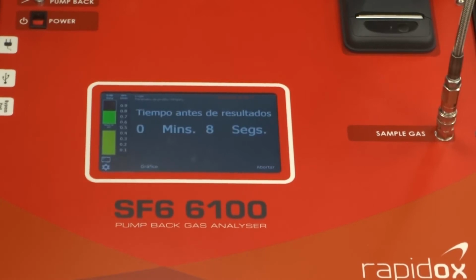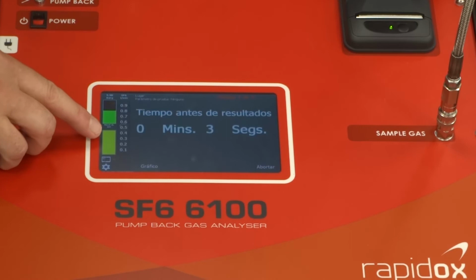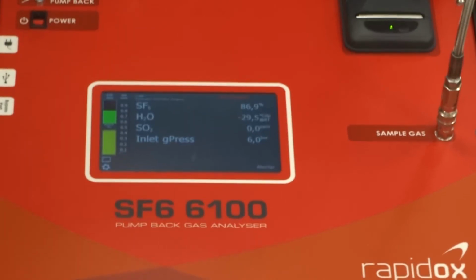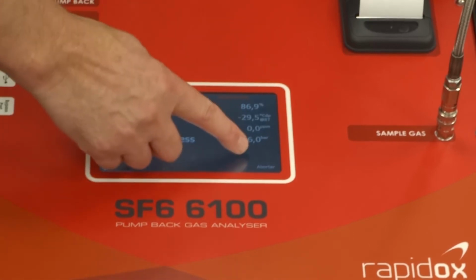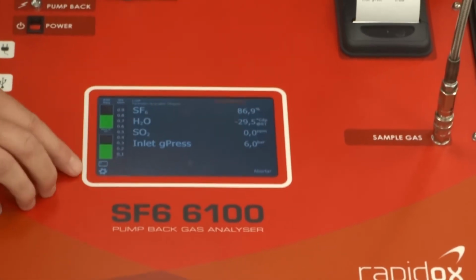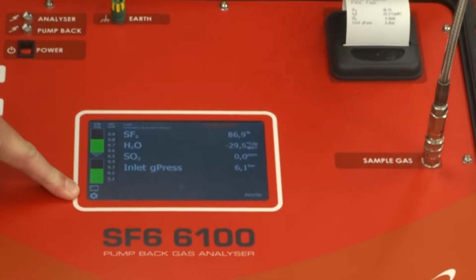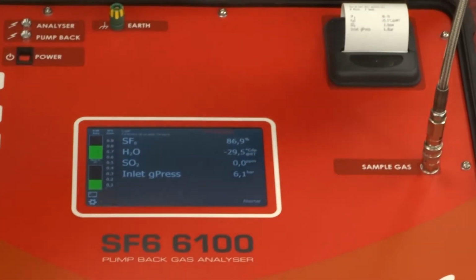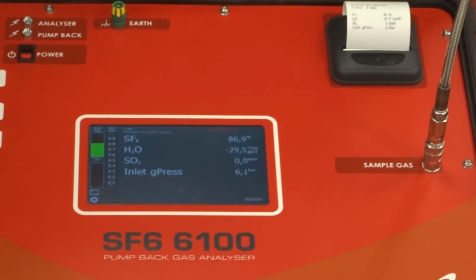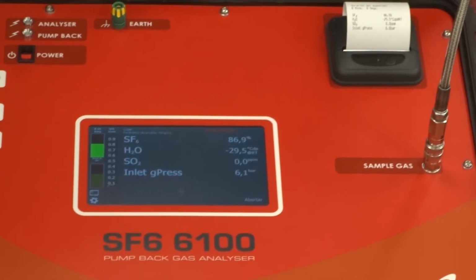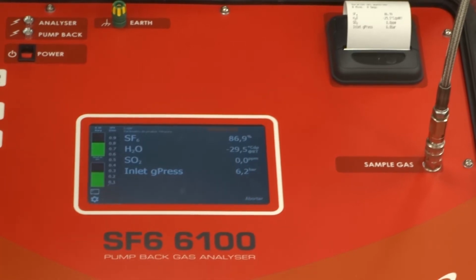Okay, so we're coming down to the last 10 seconds of the test, and you can see that the bag is going yellow because it's getting close to full. And so once the test is completed, the results are displayed on the screen, and the pump has automatically kicked in, and the gas is now being pumped back into my gas bottle, which, depending on the pressure, will take anything up to 5 minutes to complete, but it's typically a couple of minutes, 2 minutes.